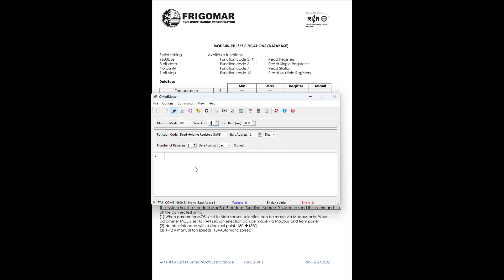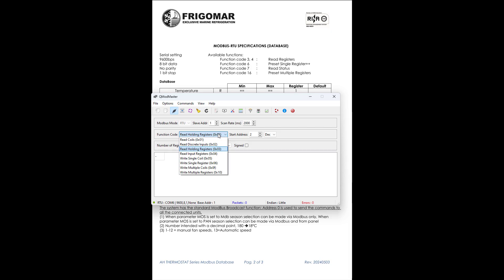Next, let's review the parameters we'll use for communication. In this case, we'll work with slave address 1, which we already identified earlier. For the start address, we need to be mindful of a small detail: in QModmaster, the start address must be entered as one number higher than the value shown in the documentation. Even though the software adds this offset internally, the request sent to the device will still target the correct register. So, if we want to read register 1 from the documentation, we enter 2 as the start address. Since we're reading a register, we'll use function code 3, which corresponds to read holding registers.